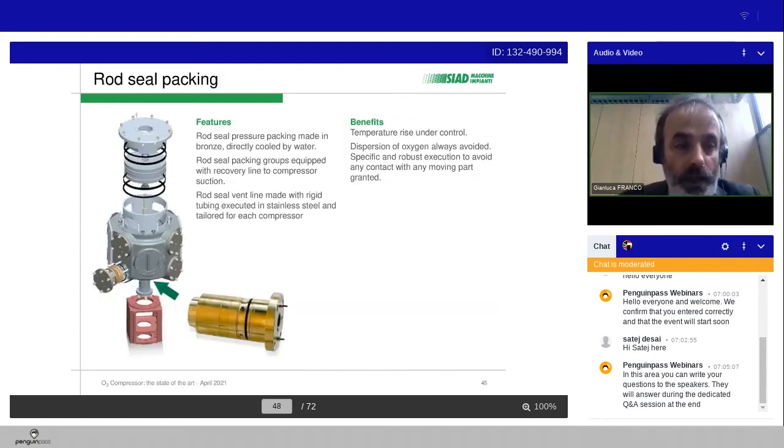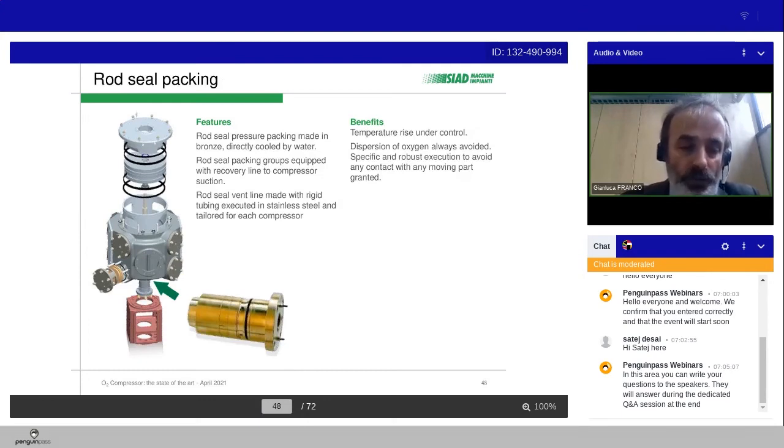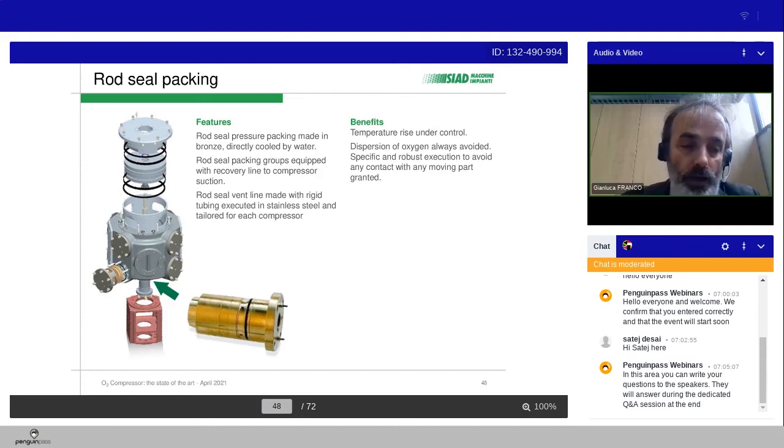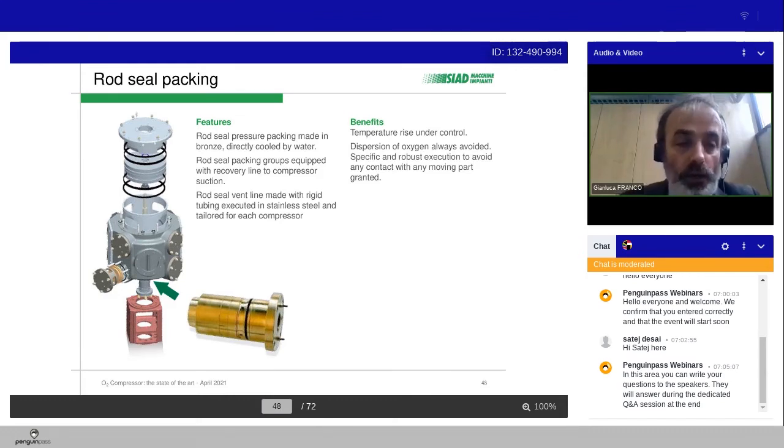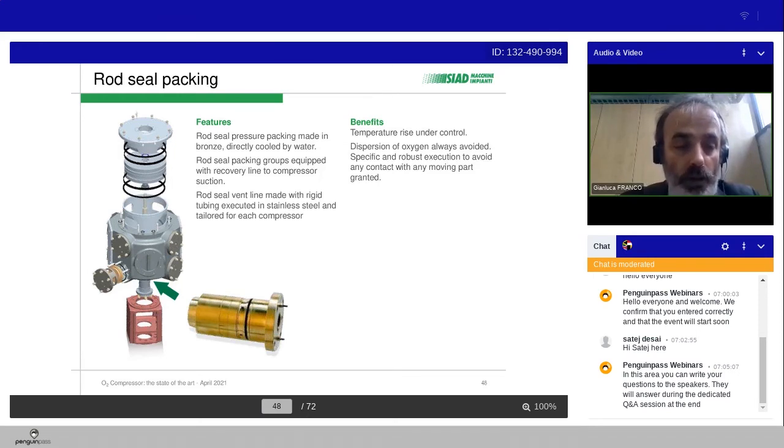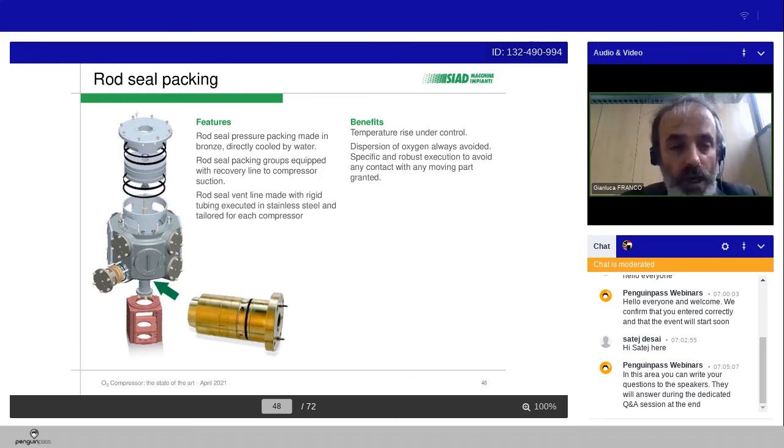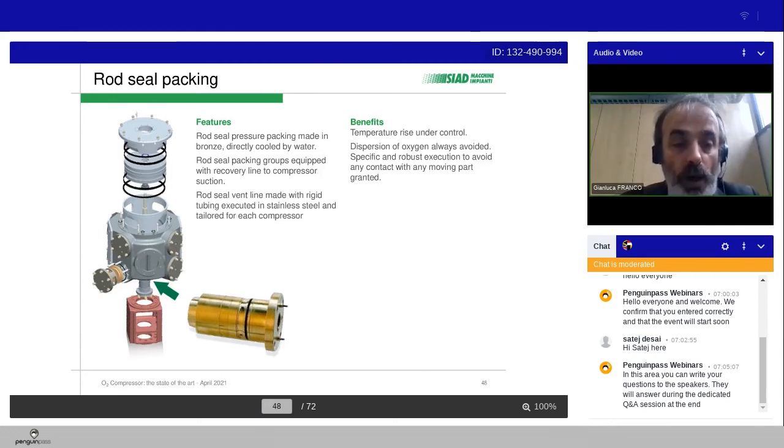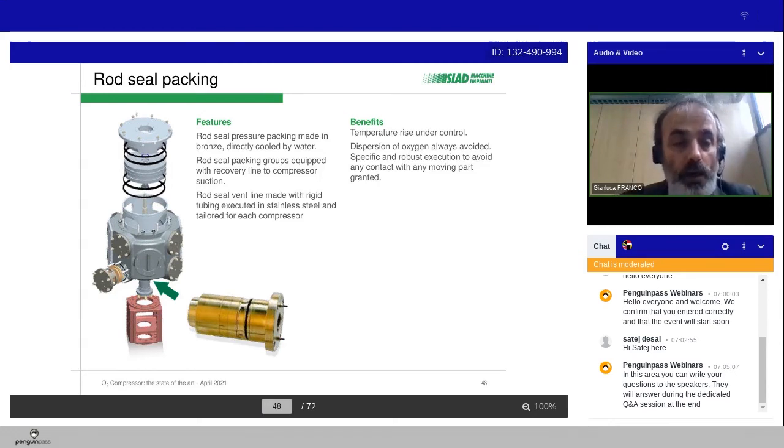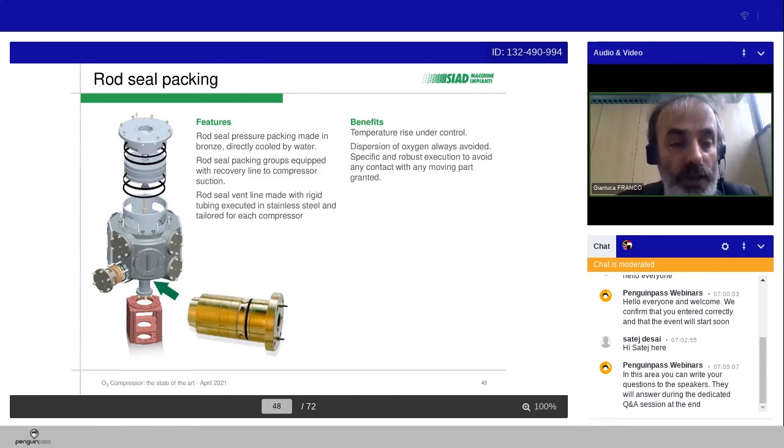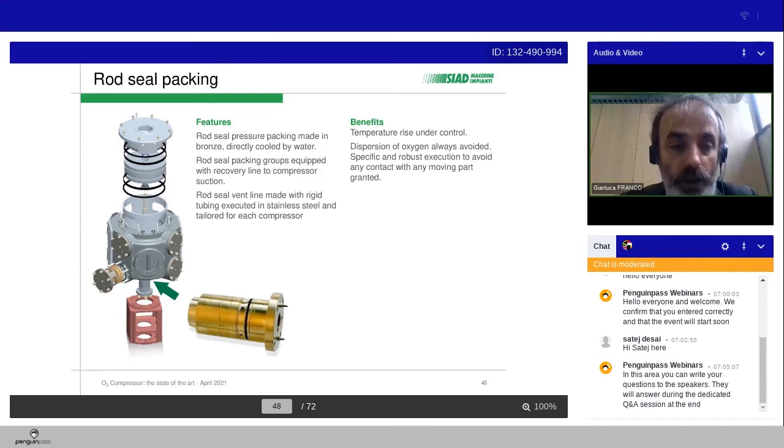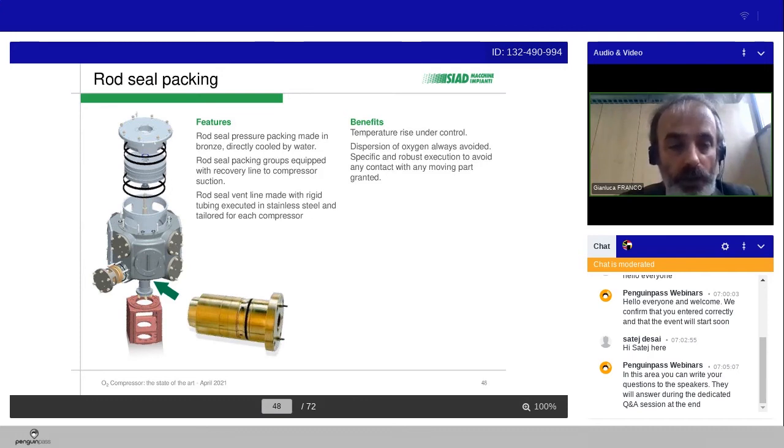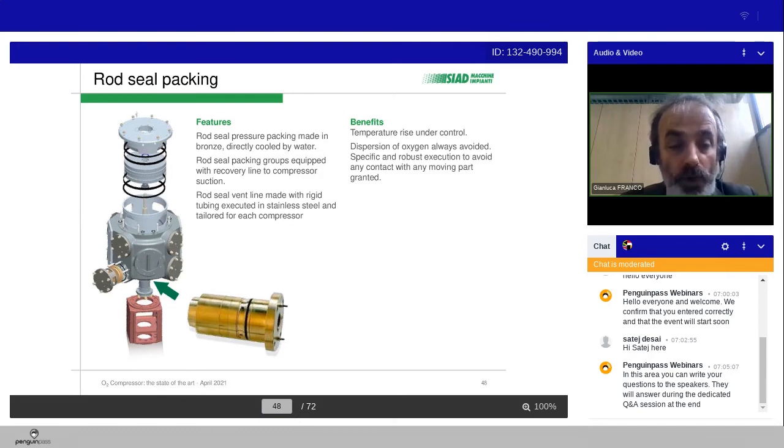The rod seal packing. The role of this element is to avoid the leakage of gas from the bottom part of the cylinder during the compression. Typically, the rod seal pressure packing are made in bronze, and according to the size of the cylinder, they are directly cooled by water. It can be equipped also with the recovery line to compressor suction to recover, eventually, some oxygen leakages and not to disperse in the atmosphere. The rod seal vent line are made with rigid tubing, executed in stainless steel, and tailored for each compressor. So this is not standard, but the standard is the philosophy of the design.